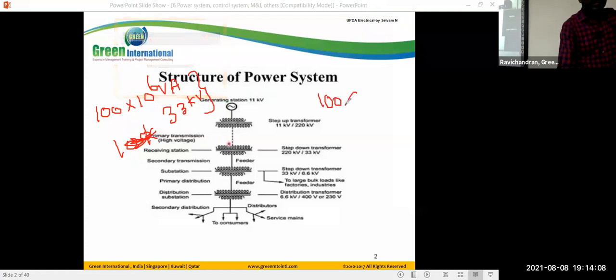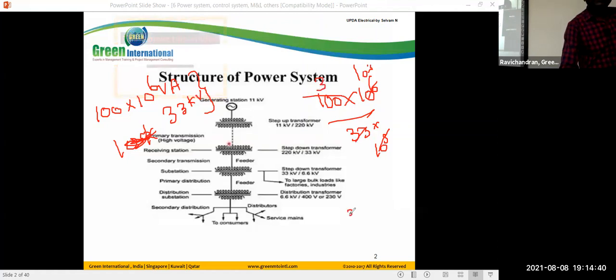For ideal conditions, assuming unity power factor, how much current will we have? It's 100 into 10 power 6, divided by 33 into 10 power 3. This is the current, assuming there are no losses, no voltage drop, and unity power factor. Under these conditions, this is the current - approximately 3000 amps. This is the voltage, this is the power, so we get this much current.